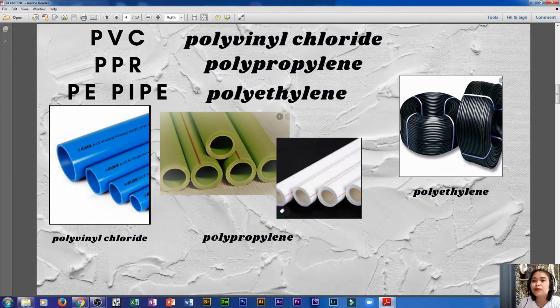And then the polypropylene or PPR is new, not very new, but we use this type of piping for hot and cold piping. Here in the Philippines, wealthy people, even if they don't use a centralized or solar water heating system, even just wall mounted, still use PPR. Why? Because PPR is less prone to leakage. With PVC, the connections leak easily. Some put solvent cement on PVC connections, but it is still prone to leaking, and PVC breaks easily compared to PPR. Why? Because joining PPR requires a different equipment, which plumbers call a plancha.